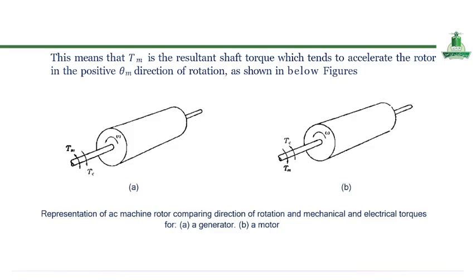The direction of torques and rotation can be understood by comparing generator and motor operations. In a generator, the mechanical torque acts to drive the rotor forward while the electrical torque opposes this motion. In a motor, the situation is reversed: electrical torque drives the rotor and mechanical torque acts as a load. These relationships are illustrated in two figures showing the direction of rotation and the interaction between mechanical and electrical torques for both generator and motor operations.